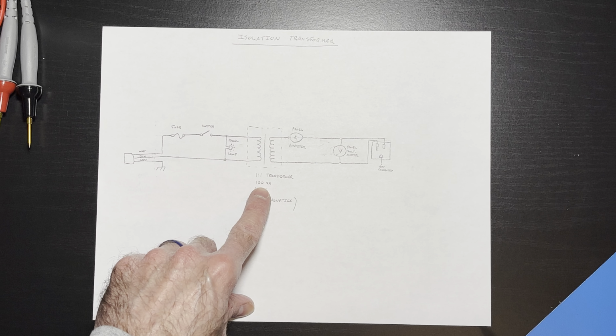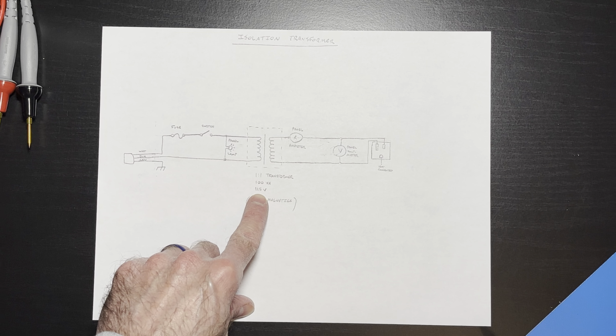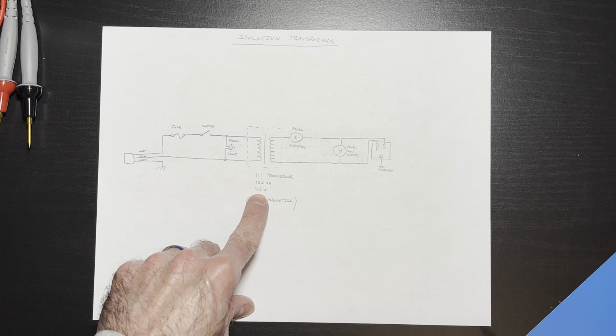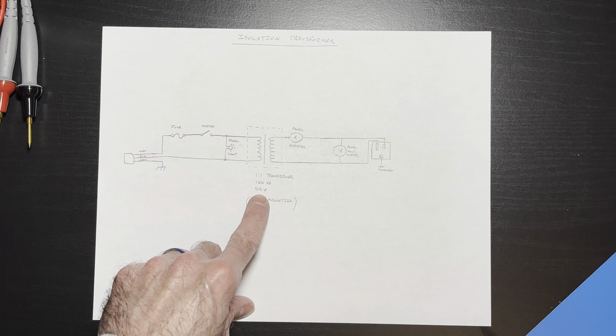It's rated at 100 volt amps at 115 volts. So if you do that, 100 volt amps at 115 volts, that's roughly 0.86 amps, which is why I put on the front panel 0.8 amps maximum.